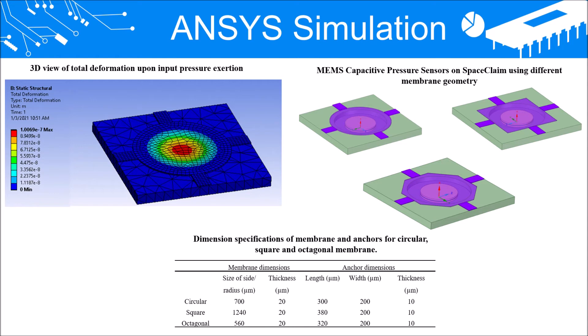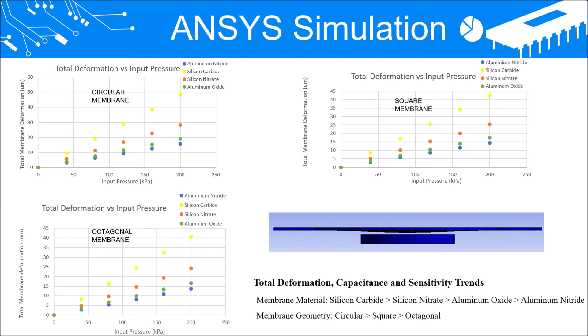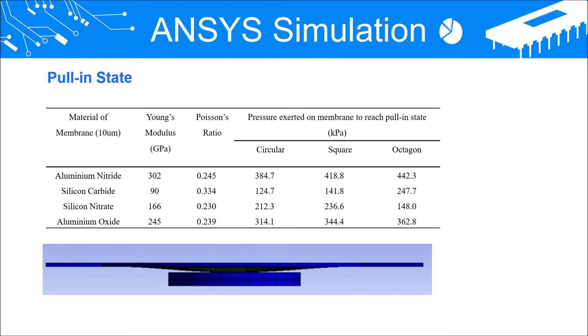MEMS Capacitive Pressure Sensor using different membrane geometry was designed on the interface with its respective dimension specifications of membrane and anchors listed in this table. Membrane deflection results show that circular membrane has the highest deflection, followed by square membrane and then octagonal membrane. For comparison between different membrane materials, silicon carbide shows the highest membrane deflection, followed by silicon nitride, aluminium oxide, and finally aluminium nitride. High membrane deflection value leads to high capacitance and high sensitivity value. The pull-in state of the sensor, whereby the membrane deforms upon maximum pressure exertion and touches the upper electrode, is also shown.